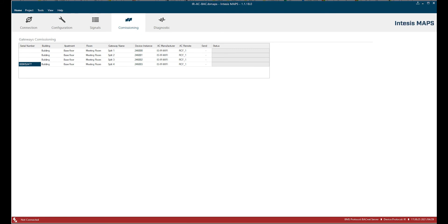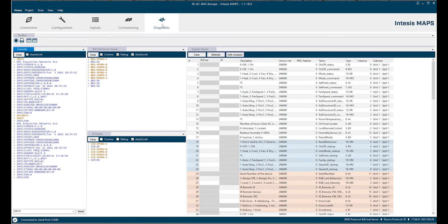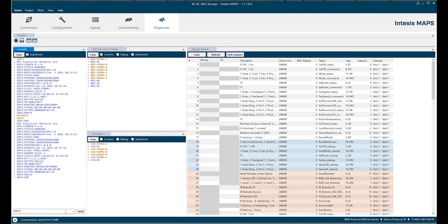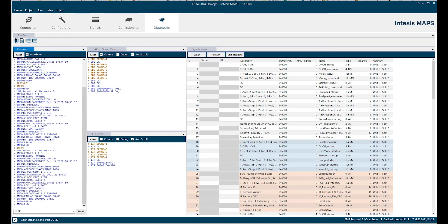Once the device is commissioned we can do some diagnostics in order to check if everything is all right. I reconnect the device. We have connected the device number 4. So the split number 4 I go to diagnostics and here we have several windows which shows us some different things about what's going on with the device. On the left side we have device console. This has some basic information of the device. We can enter here some codes. This is mostly for troubleshooting. So if you get in touch with our technical team, they will certainly use this console for checking some information in the device. But you can also reset it remotely or ask for information of the device.